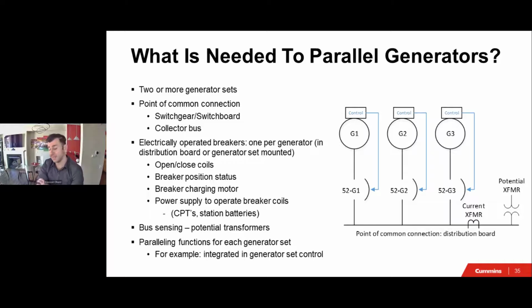We need to have some bus sensing depending on the voltage, right? If it's a medium voltage, we need to step that down. Obviously, we can't bring 4160 or 13.8 to our genset controls, right? Those operate on lower voltage. And then we need the paralleling functions that I described: the synchronizing, the load sharing, the arbitration, the protection. And what we can do is have all of those integrated on one microprocessor board that's just the size of your iPad, like a 12-inch iPad or so, and that can be integrated on the generator sets.